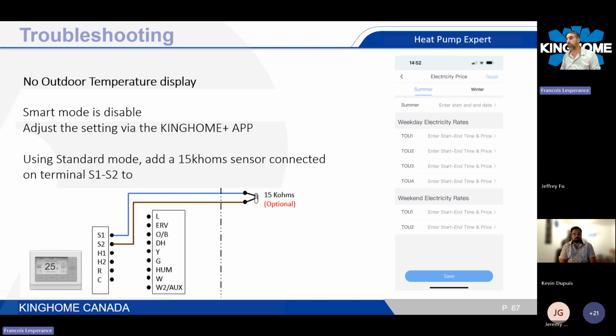So if there's no outdoor temperature display at the thermostat, it means two things. There are two ways to activate the outdoor temperature. One is via the app, using the smart control. If smart control is disabled, we will lose the location and the Wi-Fi settings. You are still able to control the thermostat via the app, but it will use the location of your device. So basically the outdoor temperature will not be displayed accurately, or it will show like 0 degrees Celsius.